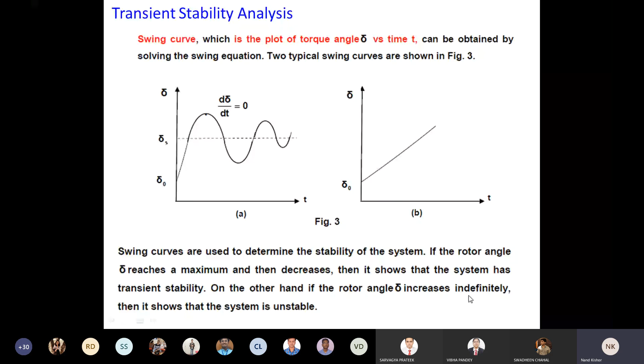So if in your study you find that d delta by dt becomes 0 at a given time, there is a probability that the rotor angle will swing back. But if, as in this figure, with respect to time the rotor angle keeps on increasing, a linear increase in d delta by dt, and it does not reach the condition of d delta by dt becoming 0, then it is understood that delta is actually increasing with respect to time. And this is the case of instability in the system, right? In that case, the rotor angle will keep on increasing indefinitely, and the system would become unstable.